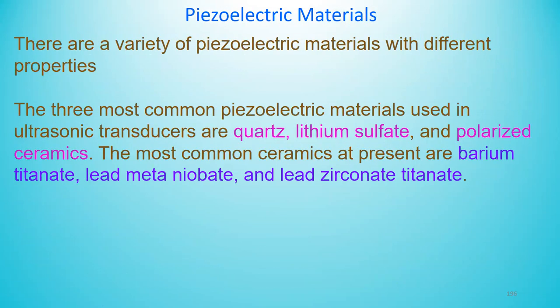There are a variety of piezoelectric materials with different properties. The three most common piezoelectric materials used in ultrasonic transducers are quartz, lithium sulfate, and polarized ceramics. The most common ceramics are barium titanate, lead metaniobate, and lead zirconate titanate.